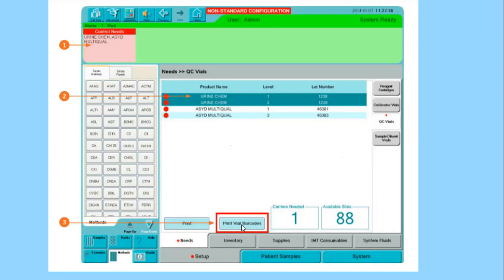You're going to hit these print vial barcodes, and we split our QC from 5 ml bottles into 2 separate containers. So control level 1 will have two 2.5 ml bottles. One will go on this Vista, and then we also have a second Vista at this location, and the other set will automatically go on the other one. We just don't do enough volume, and they will expire faster than we use them, so that's why we split them between the two machines.